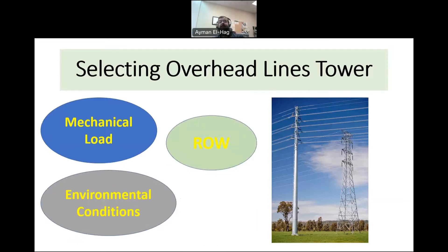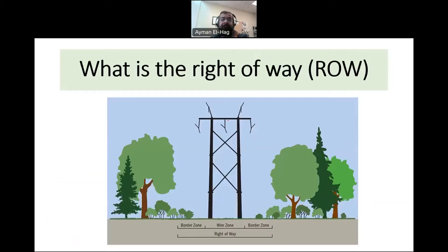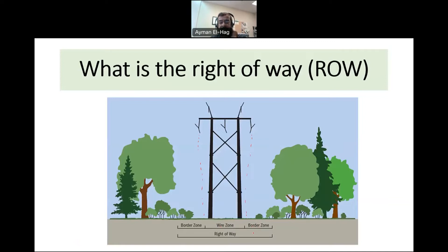Also, the right-of-way is another important parameter that we use to select the tower. But what is the right-of-way? In very simple language, if this is an overhead line, beneath the tower we have what we call the wire zone — which is the zone formed by the projection of the conductors — and then we have a border zone to the right and to the left. This whole distance we call the right-of-way.